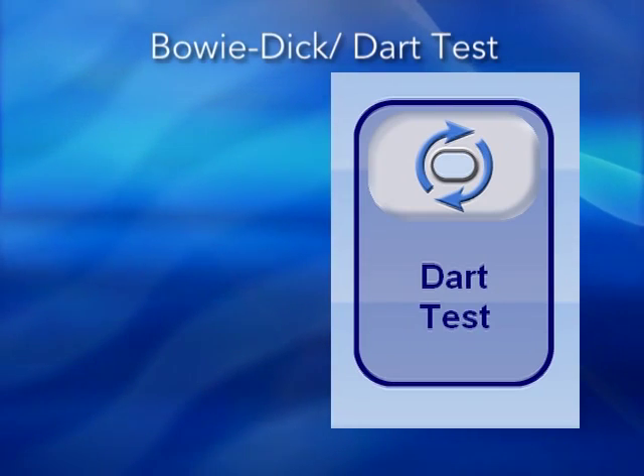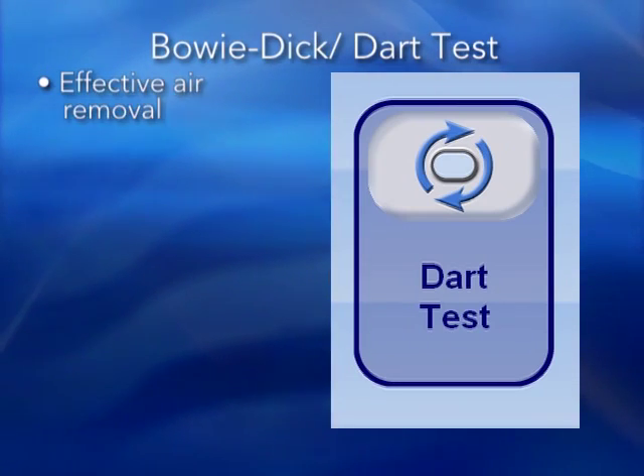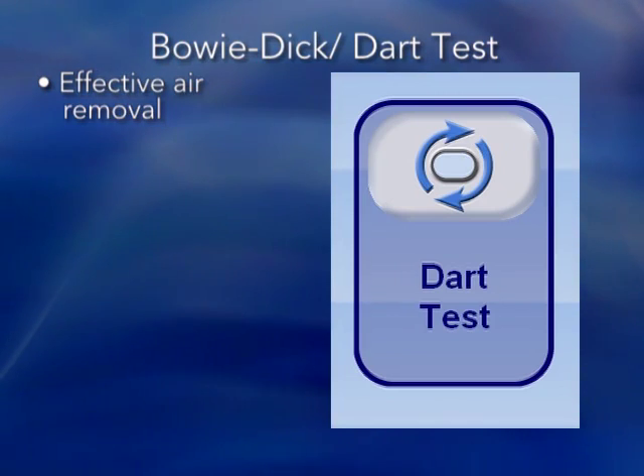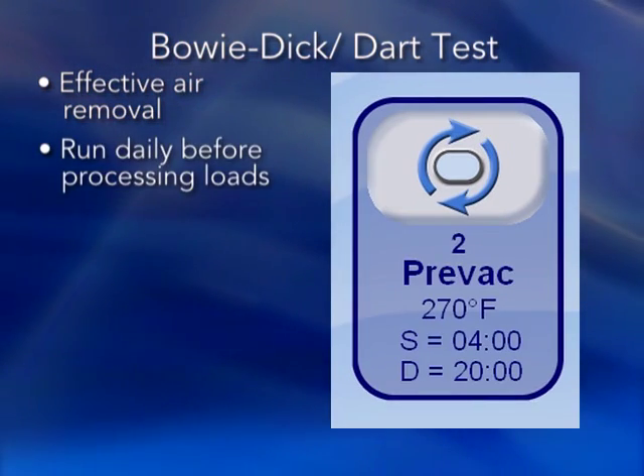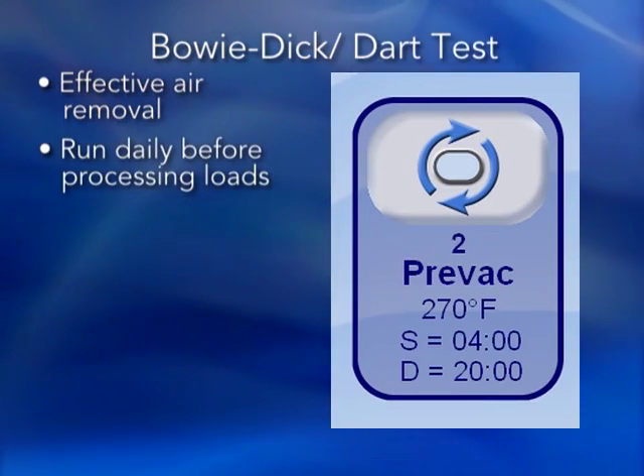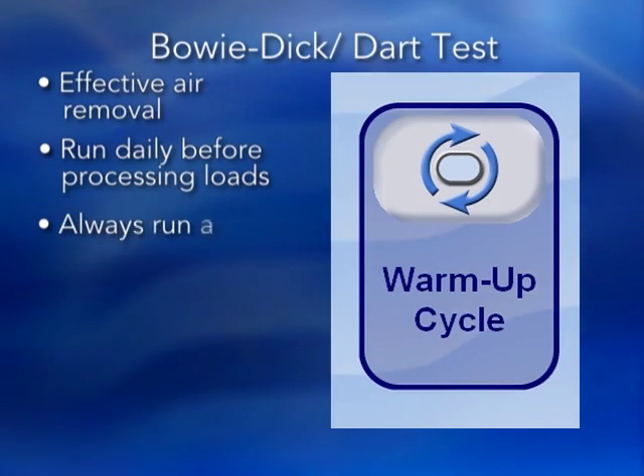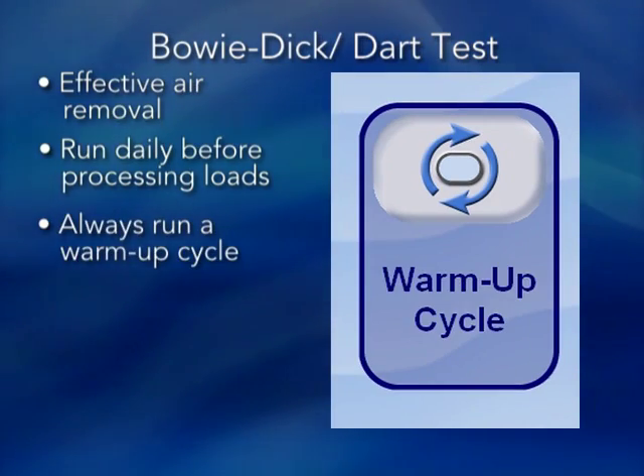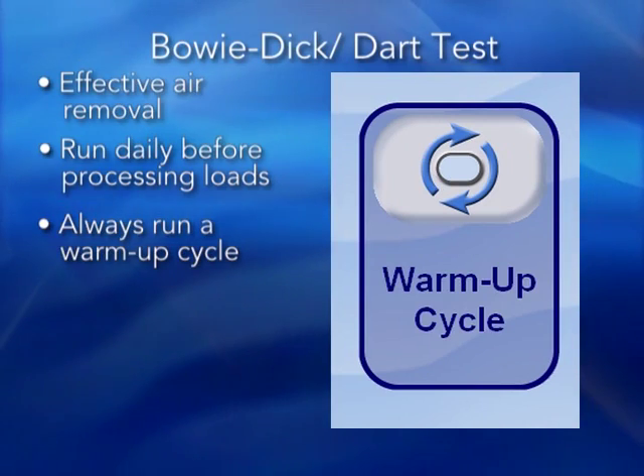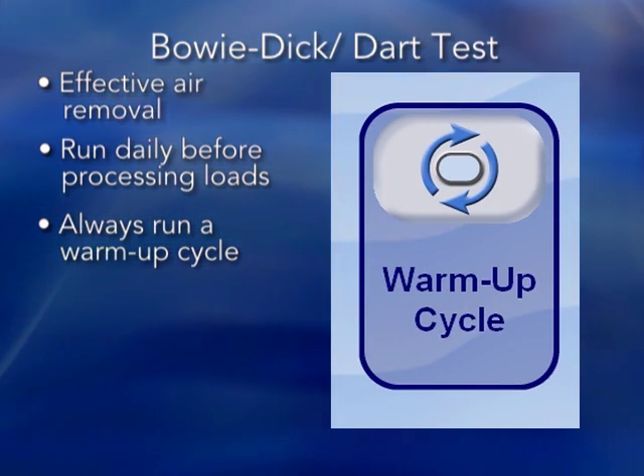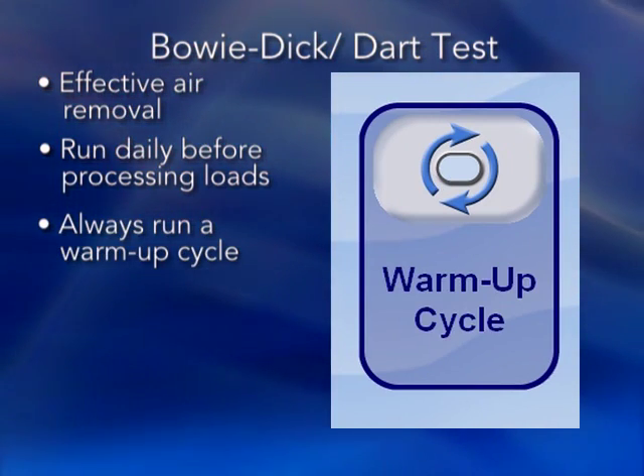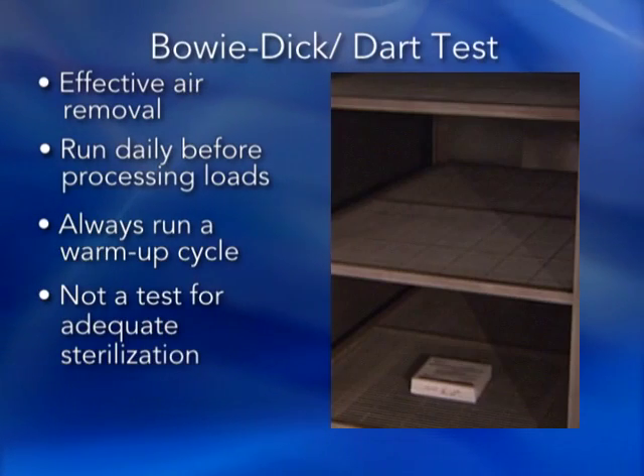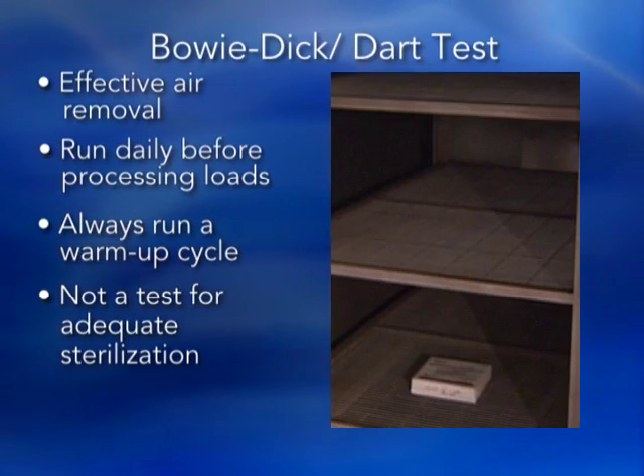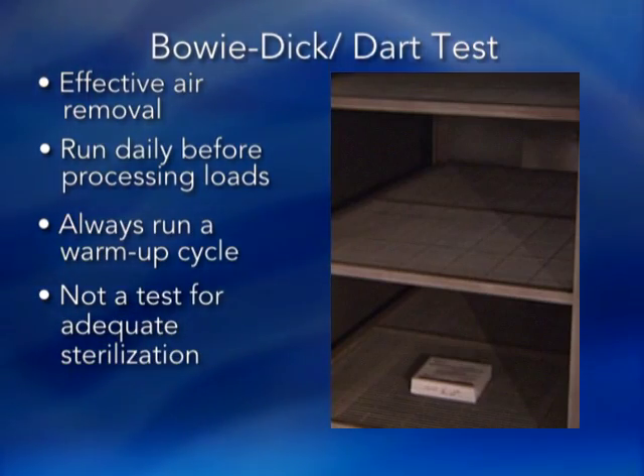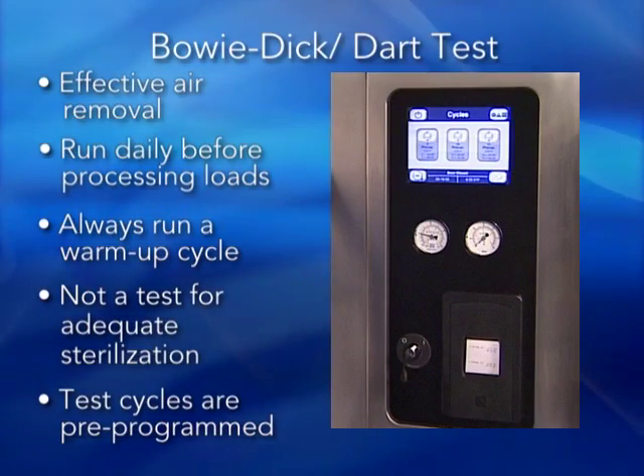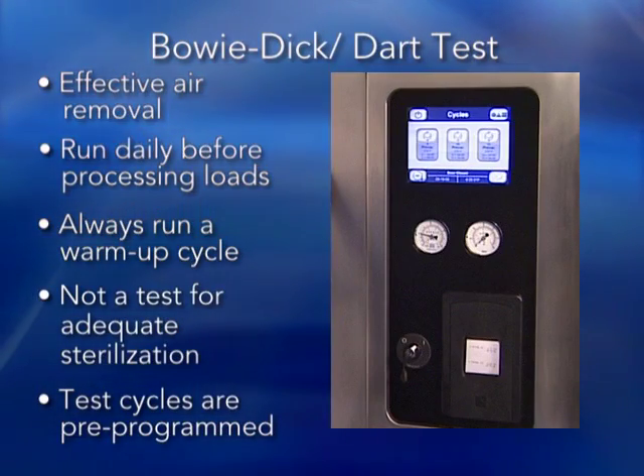The Bowie-Dick test indicates if air has been effectively removed from the chamber and challenge pack. The test should be run daily before processing any loads using a pre-vacuum cycle. To ensure valid test results, always run a warm-up cycle before performing a Bowie-Dick test to allow the machine to achieve proper operating temperature. It's important to note that the Bowie-Dick test is not a test for adequate sterilization. All test cycle values are pre-programmed and cannot be adjusted.